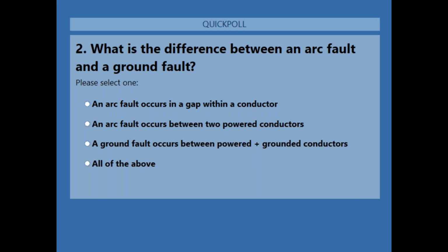An arc fault occurs in a gap within a conductor, and so that would be like if you chop the wire in half and then you hold the two ends up to each other. An arc fault occurs between two powered conductors, and so let's say you have a leg 1 and leg 2, and then a ground fault occurs between powered conductors and grounded conductors. So there's actually a grounded conductor, could be your equipment ground conductor. Also your neutral wire would be considered a grounded conductor, or all of the above.